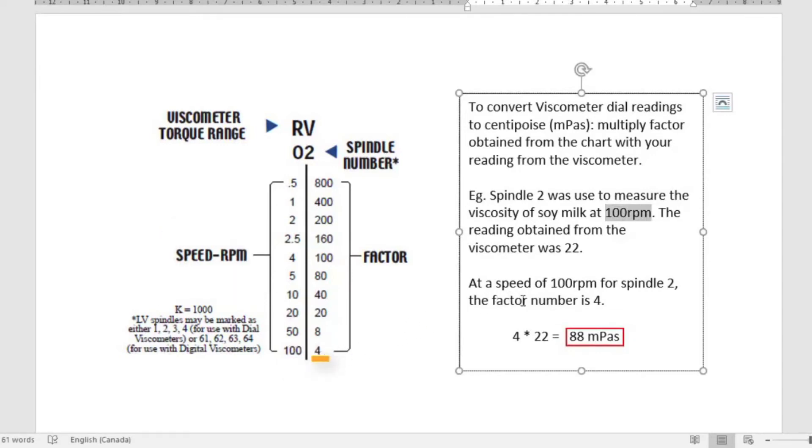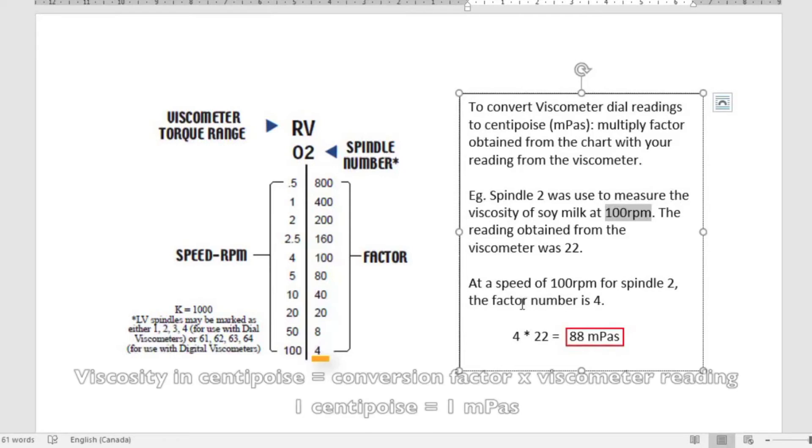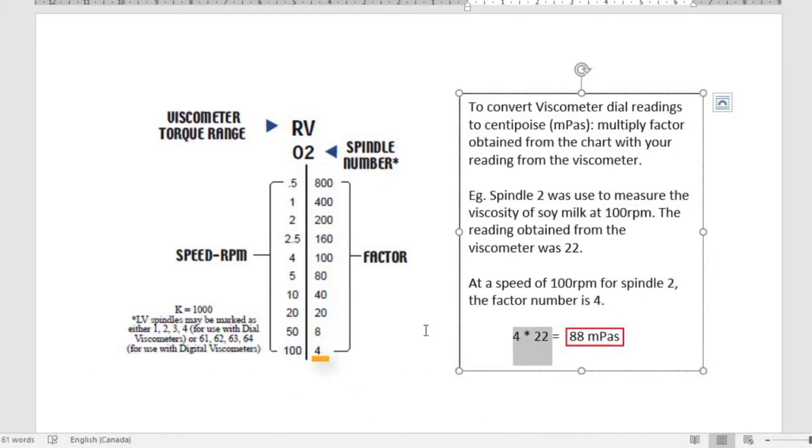To convert viscometer dial readings into centipoise, simply multiply the factor obtained from the conversion chart with the reading from your viscometer. In this example, a reading of 22 was obtained. By multiplying the conversion factor 4 with the viscometer reading of 22...